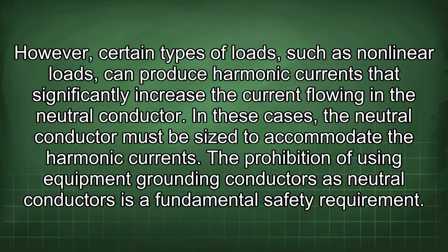However, certain types of loads, such as nonlinear loads, can produce harmonic currents that significantly increase the current flowing in the neutral conductor. In these cases, the neutral conductor must be sized to accommodate the harmonic currents.